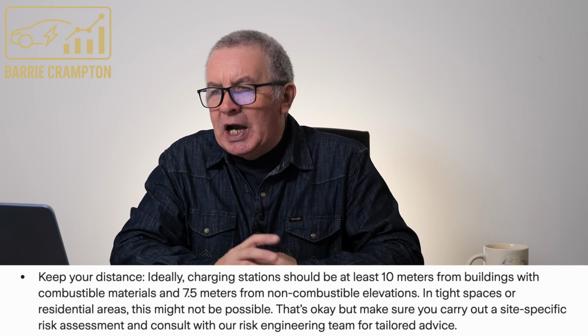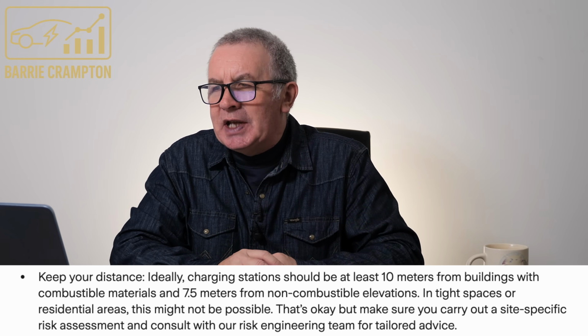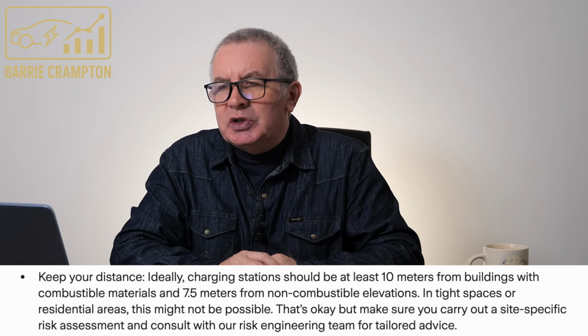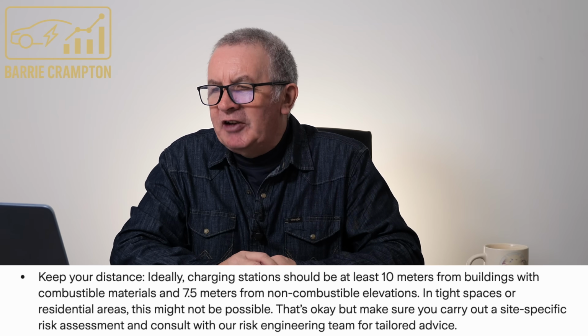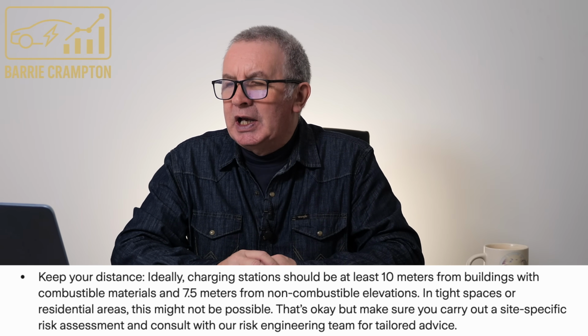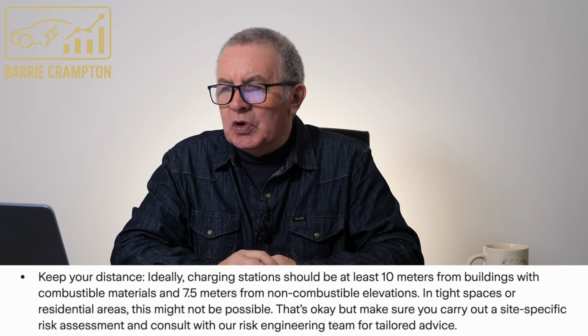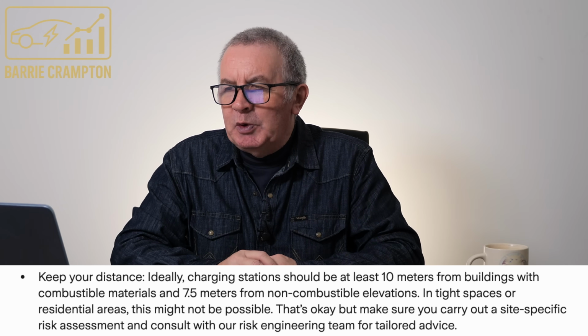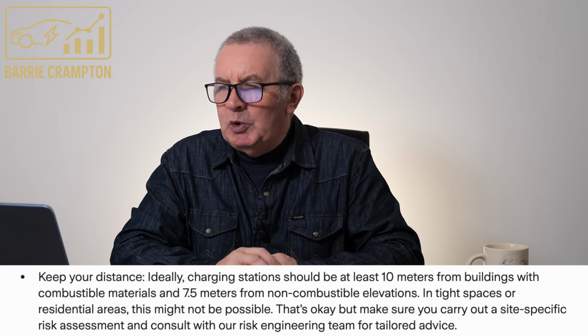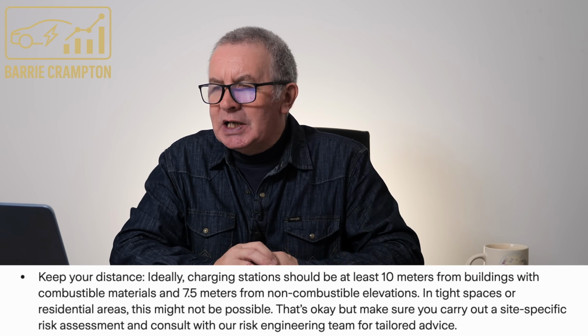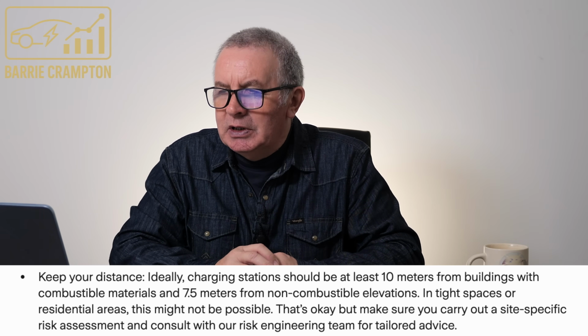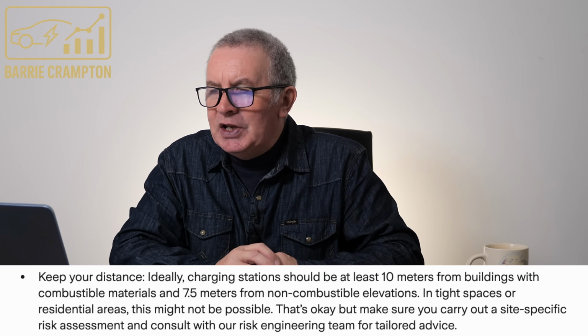Keep your distance. Ideally, charging stations should be at least 10 metres from buildings with combustible materials and 7.5 metres from non-combustible elevations. In tight spaces or residential areas, this might not be possible - that's okay, but make sure you carry out a site-specific risk assessment and consult with a risk engineering team for tailored advice.